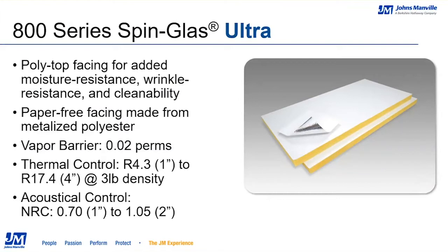Some of the benefits include moisture and wrinkle resistance and added cleanability. 800 Series Spin Glass Ultra's facing is made from metallized polyester and, as I mentioned, is paper-free. The facing has a vapor barrier of 0.02 perms and visually matches the jacket on JM's Microlock Ultra pipe insulation. Now your projects can have a consistent and clean look. 800 Series Spin Glass Ultra also has the great thermal and acoustical control you've come to expect from the 800 Series Spin Glass product line.